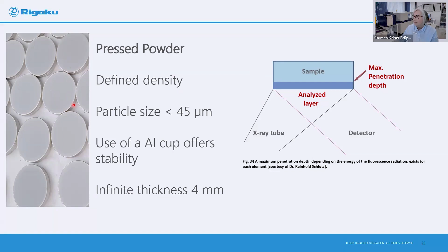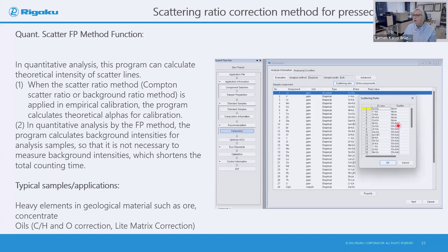So, of course, if we look at our software, we have a very nice feature in that we can use, together with our quantitative method, something that's called the ratio correction method. This means that we can measure the Compton line for that particular element and ratio it together with the analytical line. This helps us to improve the accuracy of that particular element.